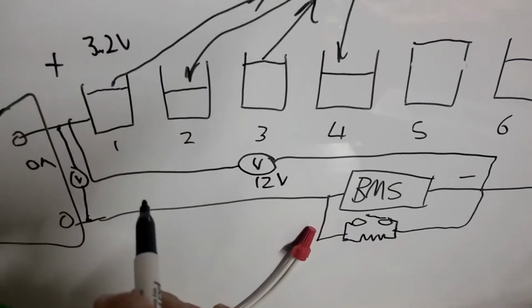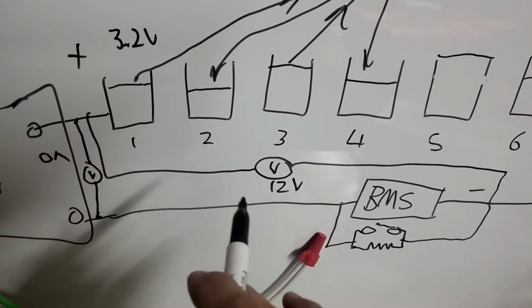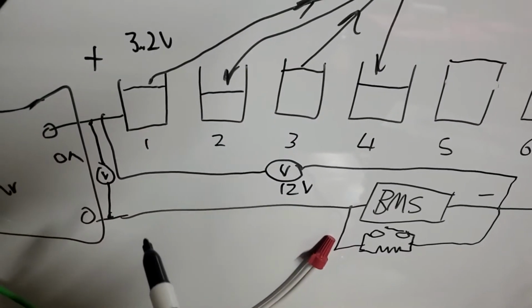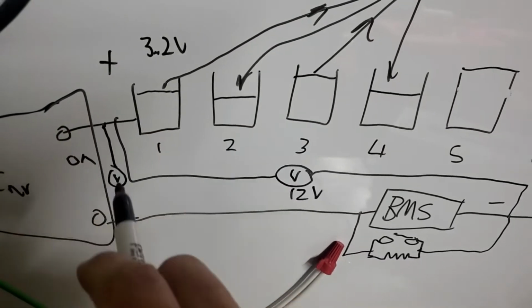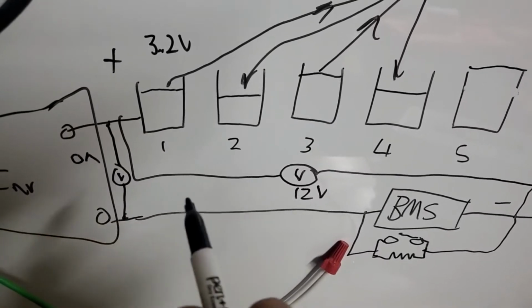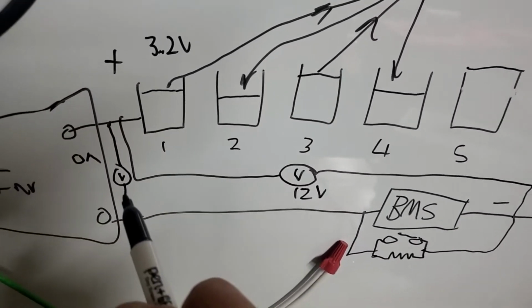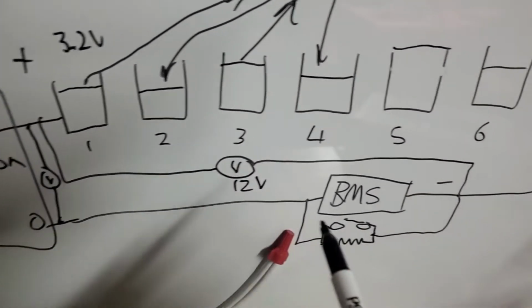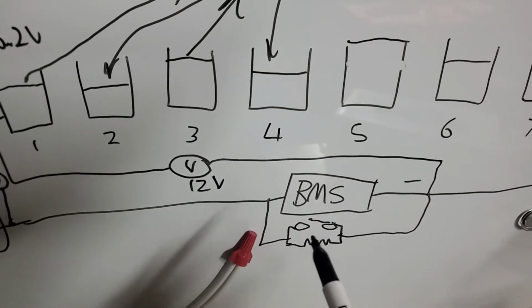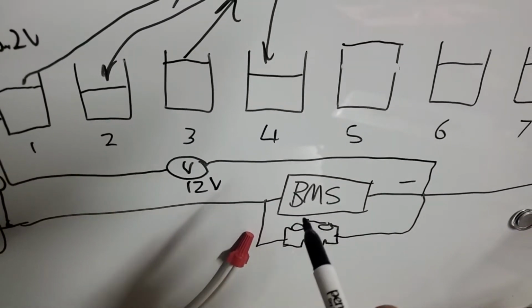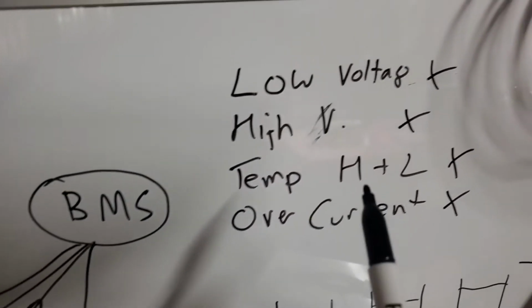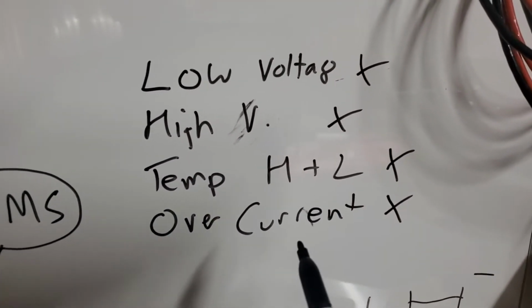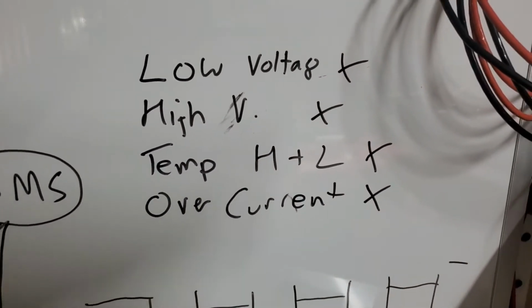That's why every time people say, my battery's showing 13 volts but the inverter won't come on, I say put a voltmeter across your inverter terminals, turn the inverter on, and read the voltage there. They go, well it's only showing 4 volts. I say yes, because you're measuring through that resistor, and the breaker inside the BMS has tripped for one of those reasons. Usually it's overcurrent, and I'll come to that right now.